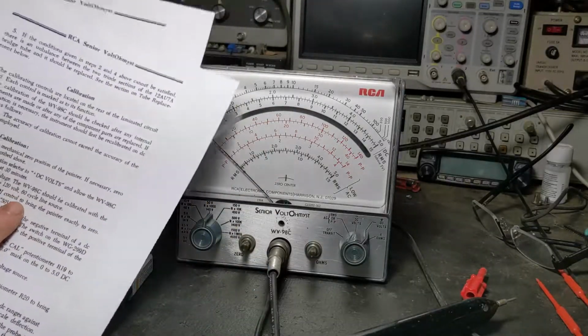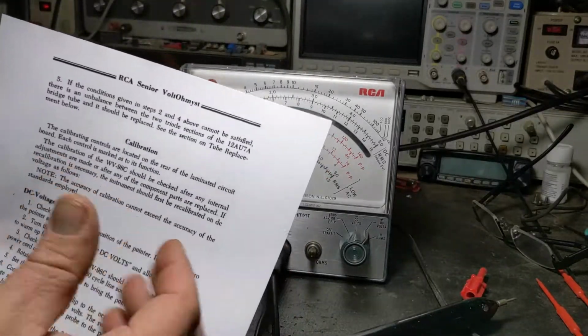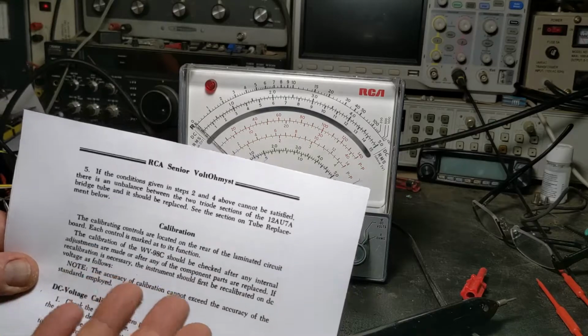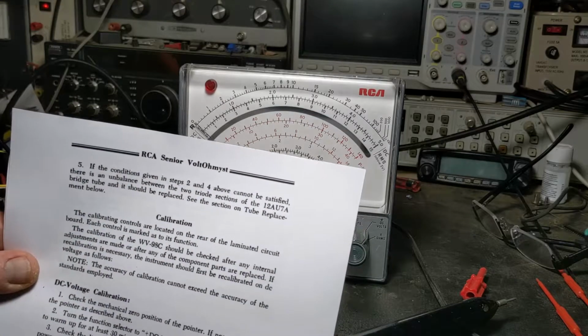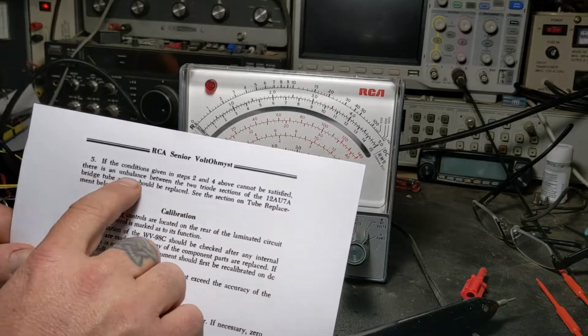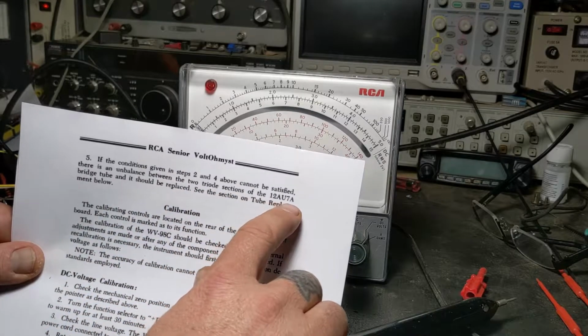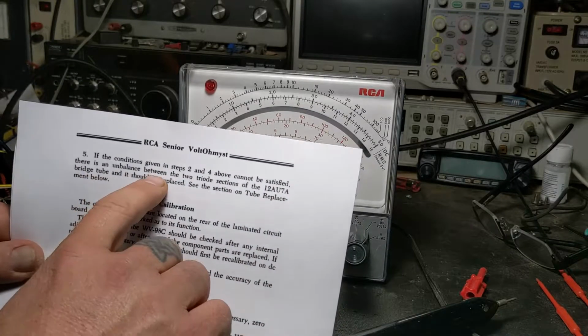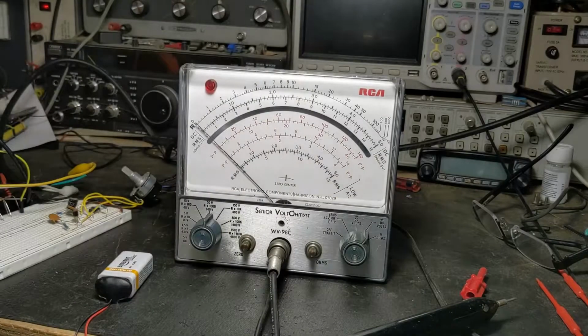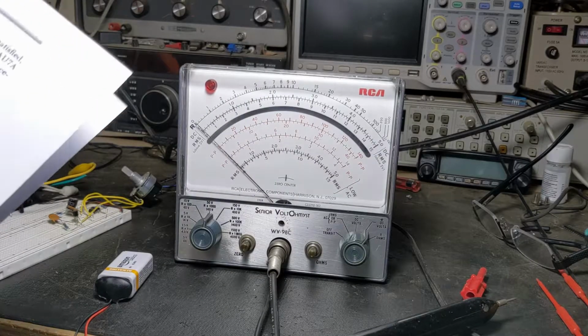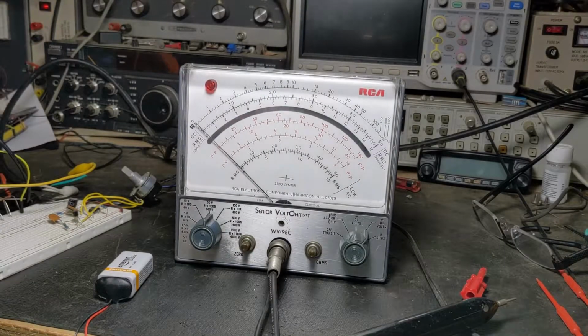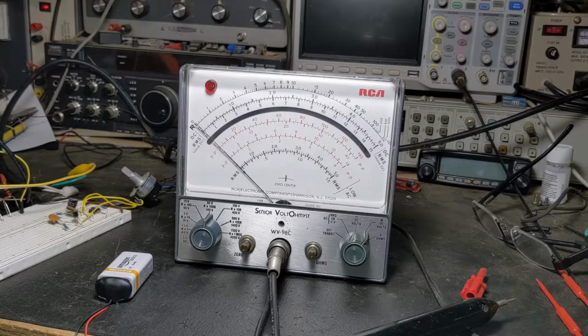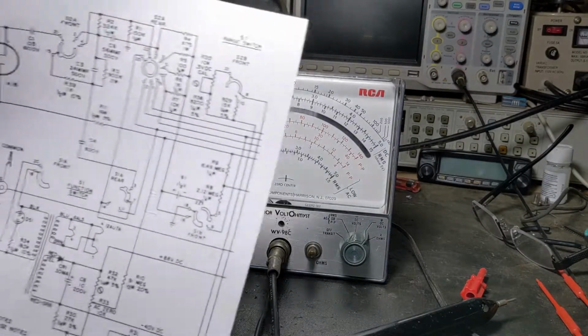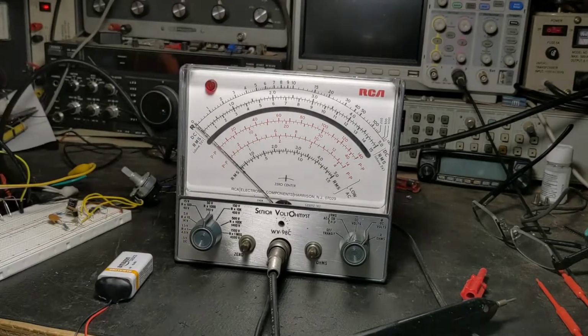So that's what they're saying there, and what it's also saying on the next page is, if you try that and you just can't get that to happen, then there's an unbalance between the two triode sections of the 12AU7 bridge tube, and it should be replaced. Now also, you could have, let's see, where did I put it? Let's look at this schematic. Wrong side.